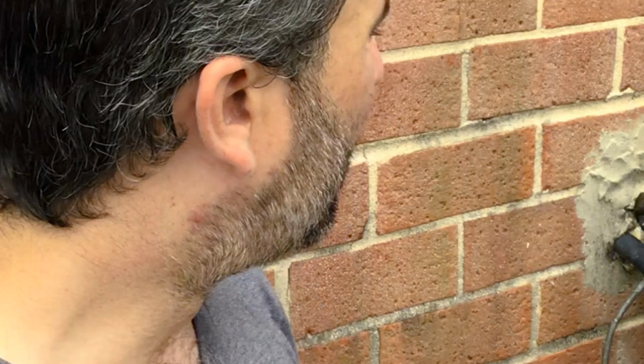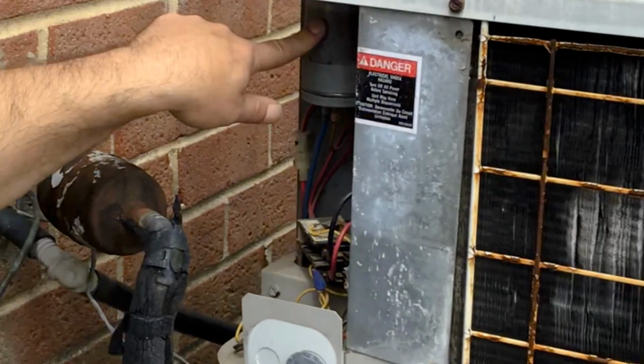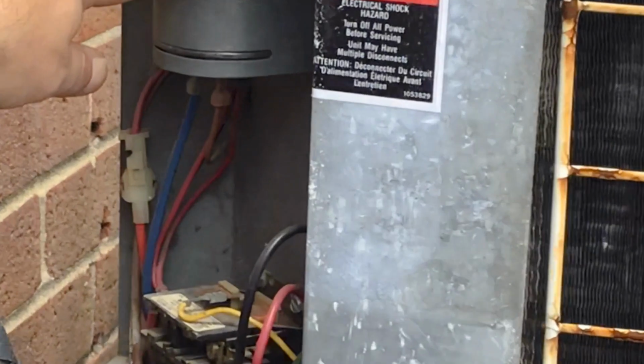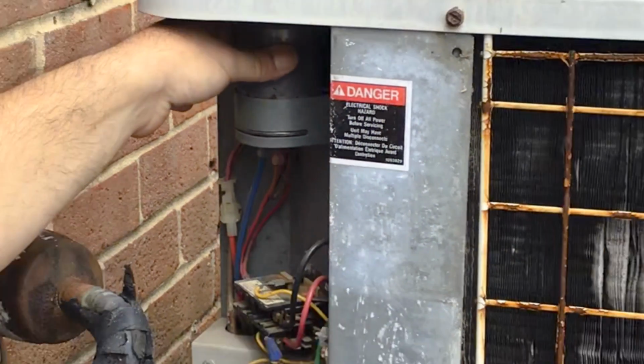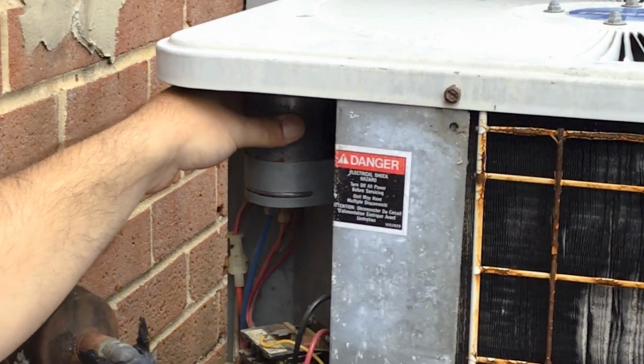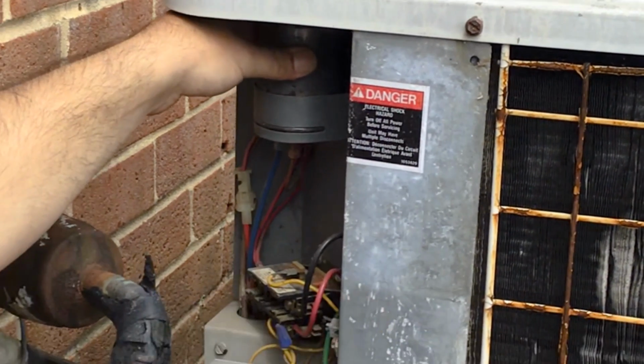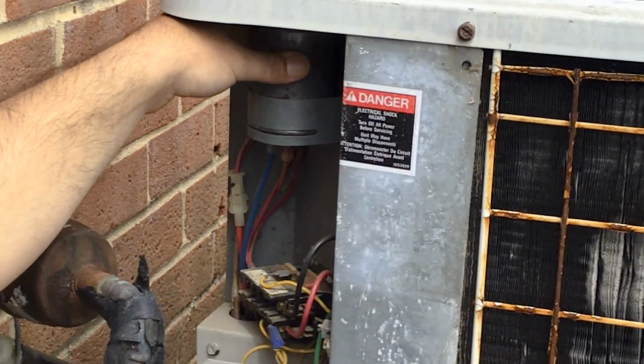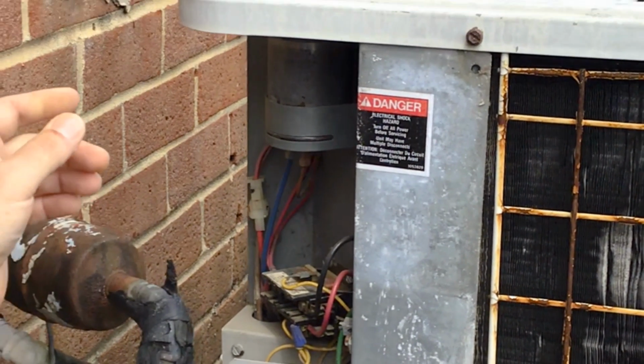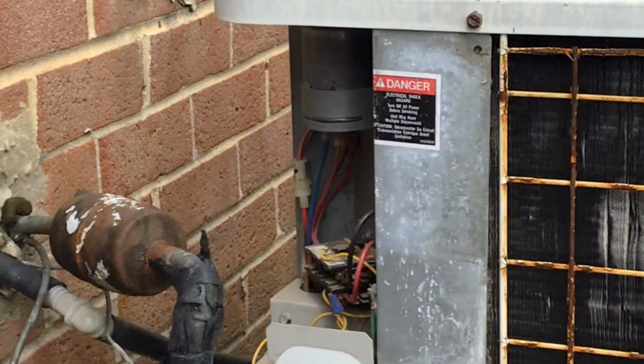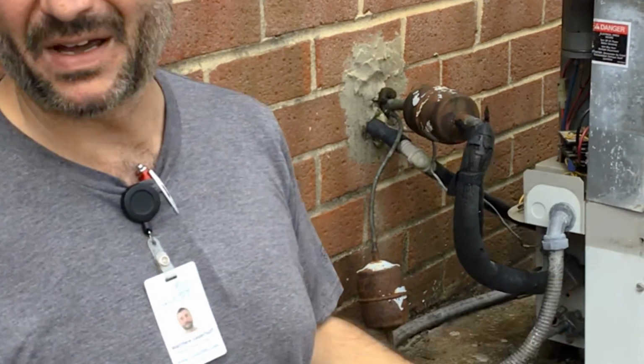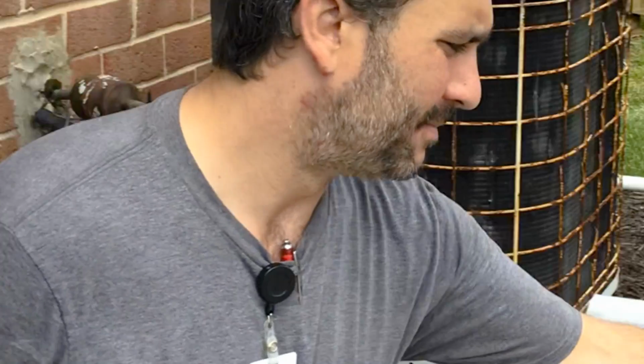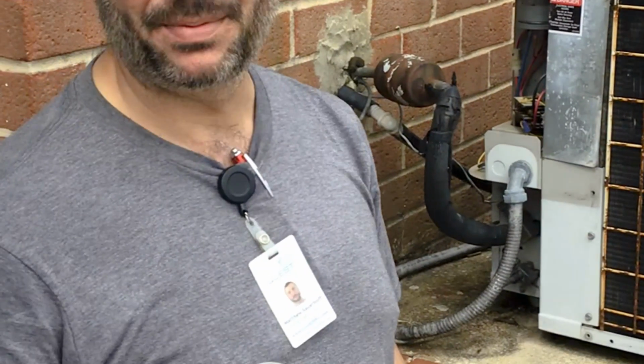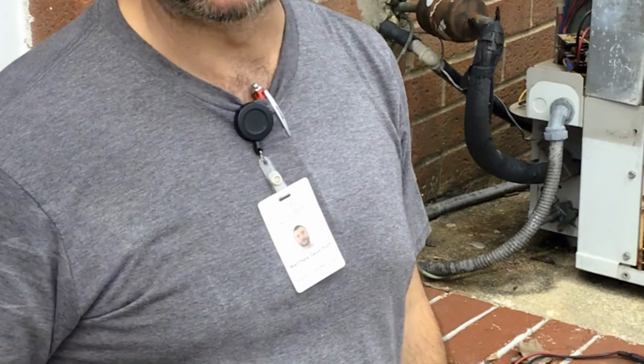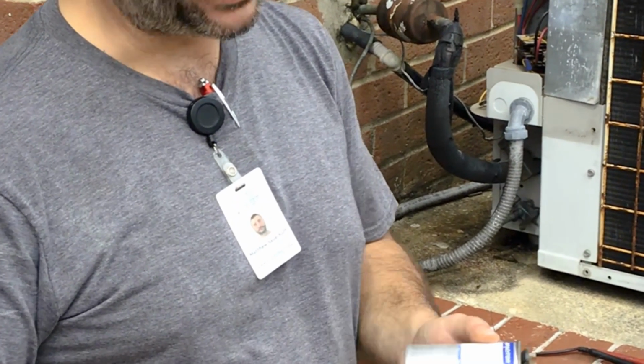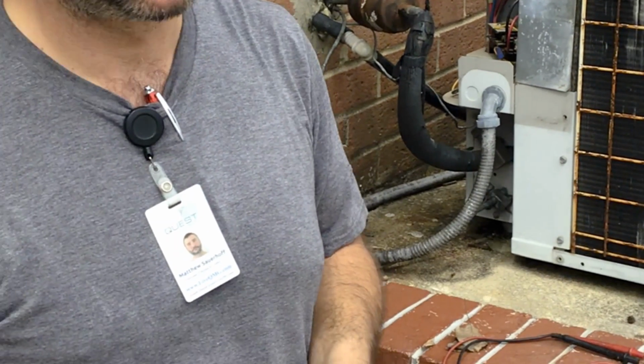Your capacitor is located somewhere inside of the service panel. Typically it's bolted to the case right here. Like I said, you always want to make sure your power's off before you mess with any of this stuff. Typically there are meters you can test the capacitor with, but I always thought that was a waste of time. These things are cheap. It takes about 5 minutes, not even 5 minutes, to put one in. They cost between $12 and $15.